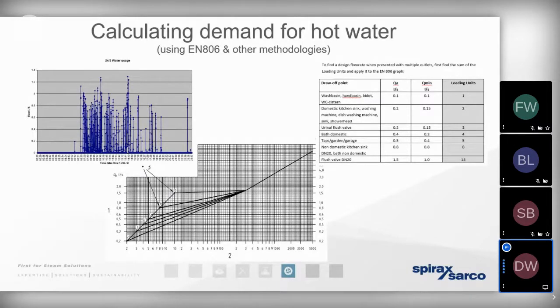So if we end up with an oversized heat exchanger, not only does it mean that the capital cost is likely to be more than it needs to be, but it means that this heat exchanger is going to be working inefficiently because it's going to be generating more hot water than the site actually needs. So together with the fact that it's going to be taking up more and more space in the plant room itself, and because of this increased mass of steel and the increased mass of water that's held in storage, we've got more radiating losses and standing losses.